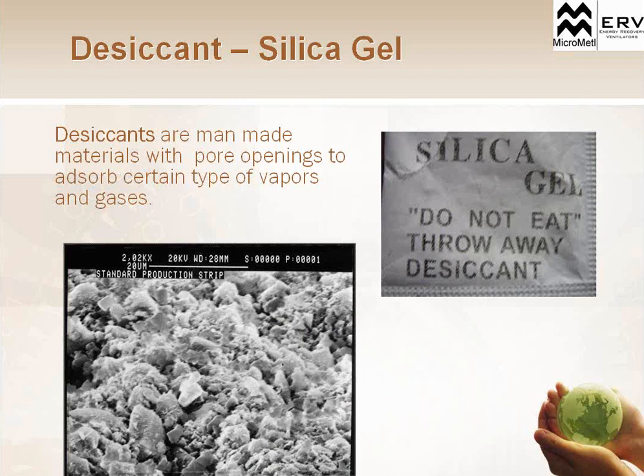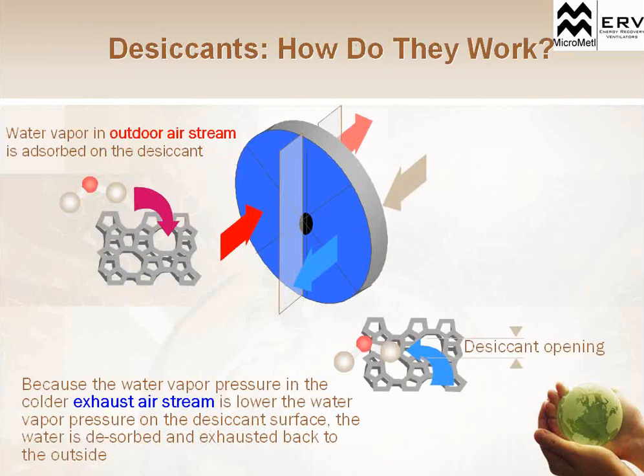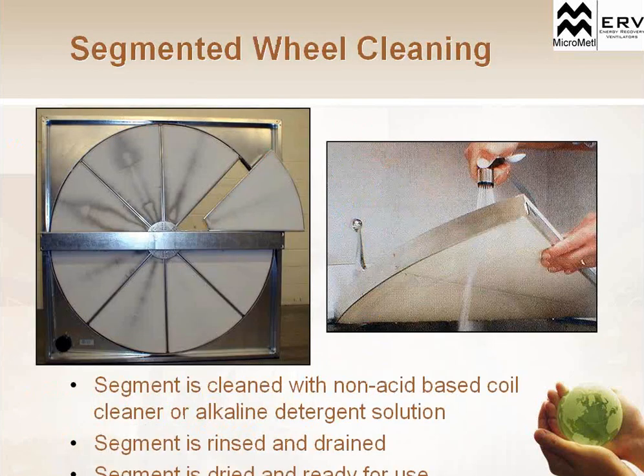A silica or a desiccant has pore openings, chemically has openings that allow moisture to be brought in. It absorbs and releases moisture very quickly. And so that's why they use different types of desiccants on these wheels, to absorb moisture and then release it. There are different types in each one of the wheels, but basically here's how it works, a chemical breakdown of a desiccant. The water vapor molecule fits inside, absorbed into the desiccant itself, but the water vapor pressure from a colder exhaust air releases that moisture back into the space. So the desiccant opens up with that colder air and releases the moisture back into the space. So it absorbs the moisture and then releases it again. And there are different types of desiccant materials, but silica is one of the most common.